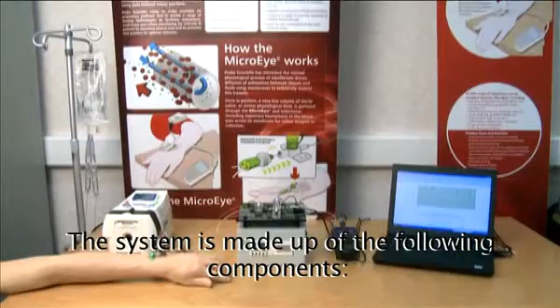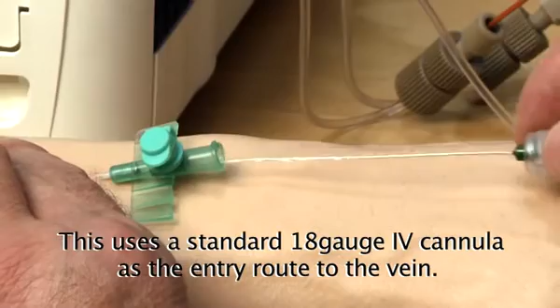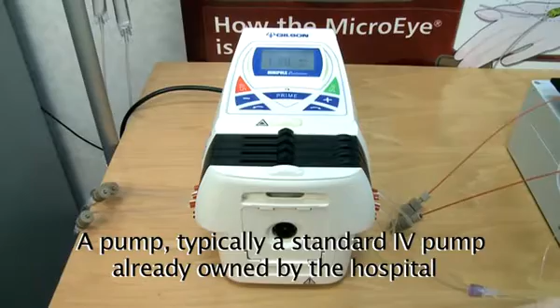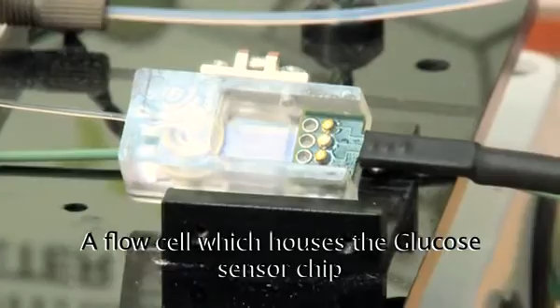The system is made up of the following components: the MicroEye body interface sampling device. This uses a standard 18-gauge IV cannula as the entry route to the vein. A standard IV solution, saline or ringers, is used as perfusate, with a container of calibrant solution of a known glucose concentration. A pump, typically a standard IV pump already owned by the hospital. A flow cell which houses the glucose sensor chip.